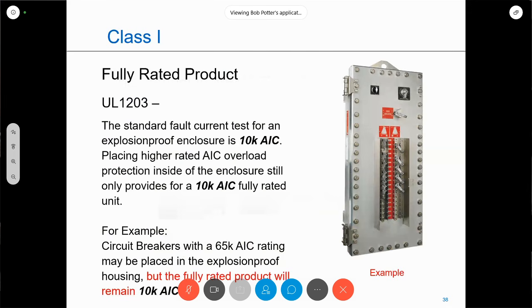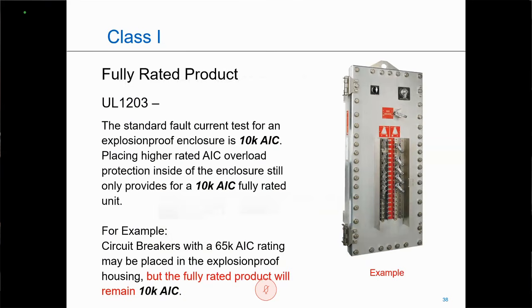Perfect. Okay. Now, we mentioned the UL 1203 test as the 4-time safety factor test, but another thing that UL 1203 provides is a baseline for our fault current rating. So the particular hazardous location NEMA 7 enclosure has a baseline fault current of 10K AIC. Now, what happens is if an application comes up and somebody wishes to achieve a higher fault current rating because of the available fault current that had been calculated, maybe they need 14K, 35K, 65K, whatever the particular fault current rating that is possible for that particular equipment.